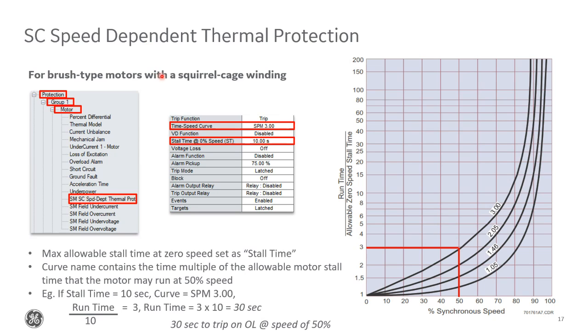Once again, here showing the settings as you would see in the EnerVista setup software. So under protection group one motor, you'll see SMSC speed dependent thermal model. The key settings that we need to consider are the time speed curve number and the stall time at 0% speed. On the right, again, we have 869's available curve selections. These curves indicate the thermal limit as a function of the speed versus how long it's allowed to run expressed as a multiple of the allowable stall time.